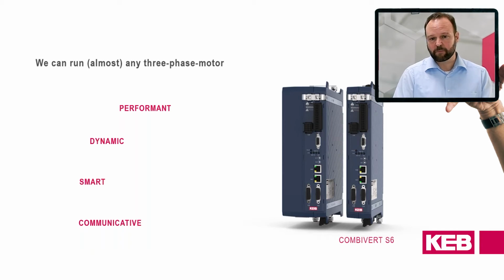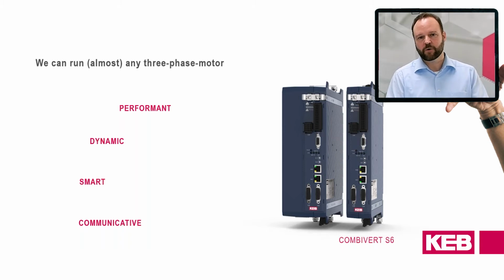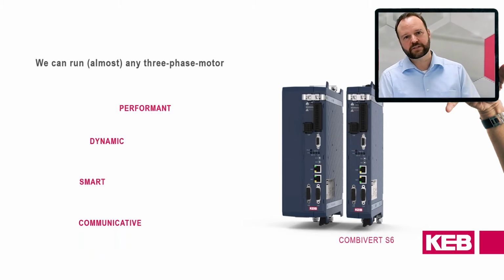As we have got a big variety in our portfolio of motors, we can, of course, handle third-party motors very well. This is one of our biggest strengths. If we talk about motors, we also have to talk about temperature sensors. Also there, we can handle different kinds of sensors like PTC, like PT1000, like different KTY sensors. And of course, you can also put your KTY sensor characteristics inside of the drive.